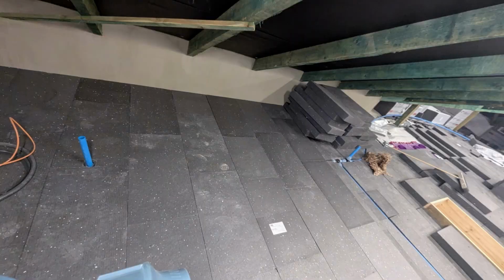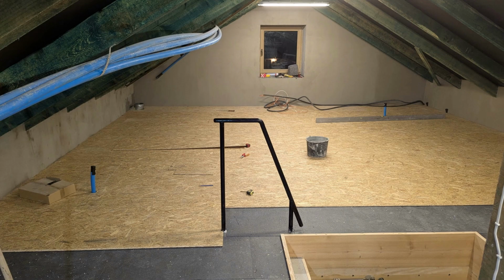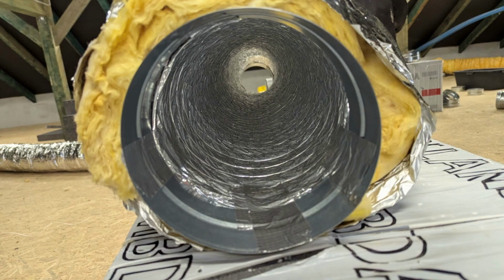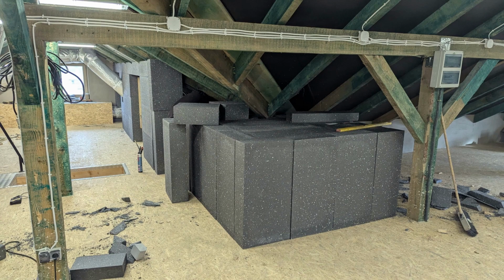Above these elements are 2 additional layers of polystyrene of the same thickness, along with 2 layers of tongue and groove OSB boards, which are laid overlapping. Part of the connection between the heat recovery unit and the distribution manifolds, both on the supply and exhaust sides, was constructed using flexible ducts to effectively minimize noise. The plenum boxes were also lined with rubber for this specific purpose. I did not use any silencers.